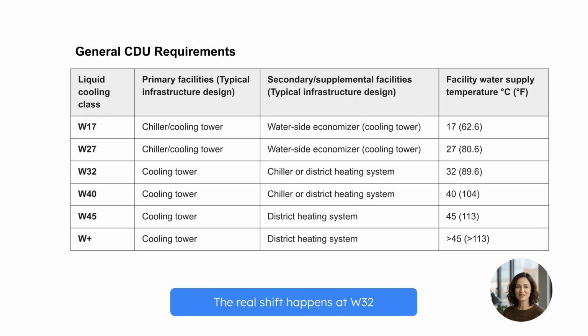The real shift happens at W32. With a 32-degree supply, notice how the primary facility switches to the cooling tower. In most global climates, W32 unlocks full free cooling. The chiller is demoted to a backup role. This is where we see massive energy savings.